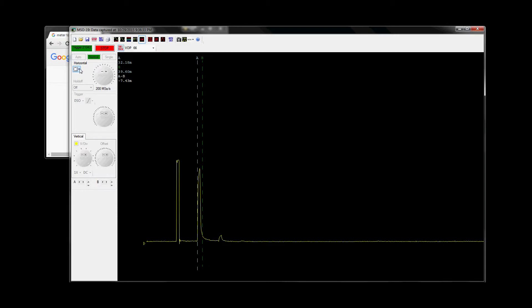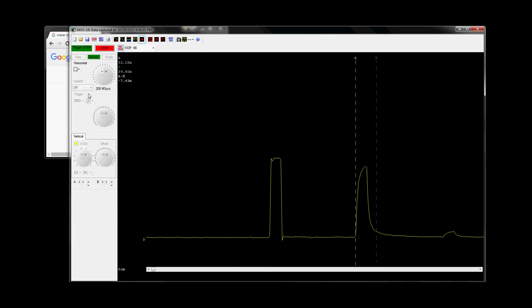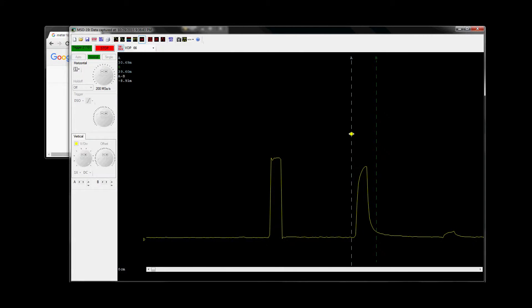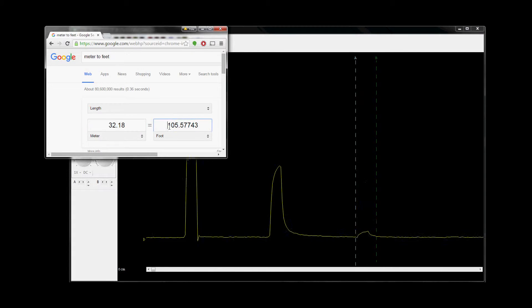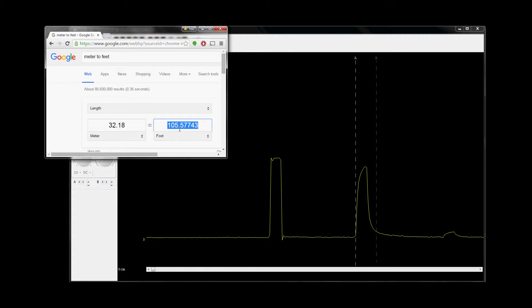Now let's zoom in a bit and measure the distance of this cable. The trigger cursor is always measured from the initial pulse, so we drop cursor A down to the inflection point. I have a distance of 32.18 meters — that's 105 feet. It's close to 100 feet because we have a little bit of propagation delay from the scope's circuitry.